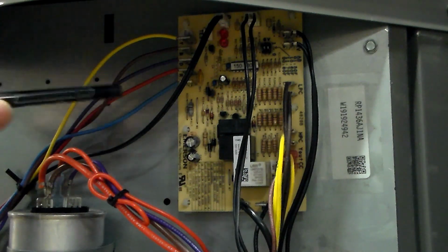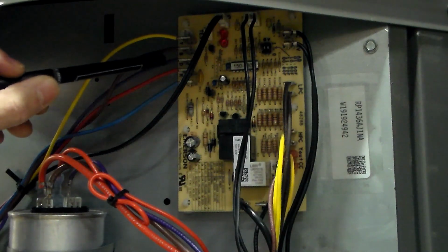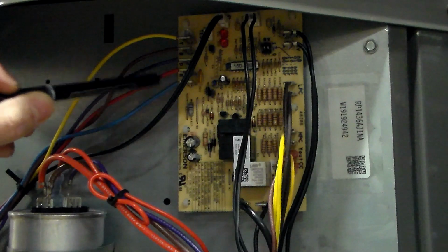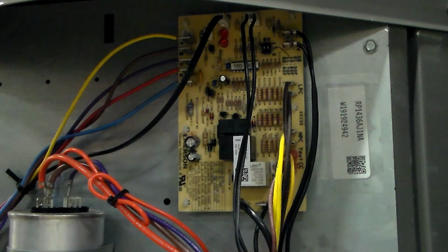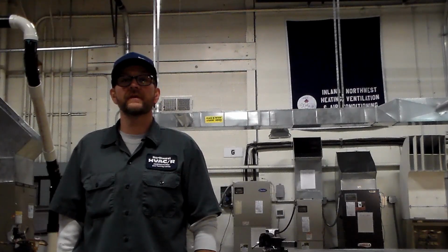You just have to understand that Rheem and Ruud do it backwards. They have the B instead of O, and they have D instead of W, but every other function on this board is exactly the same. You just have to remember that with Rheem, it's going to be sending 24 volts to the reversing valve during heating, and with everyone else, it's going to be doing that during cooling. And so, of course, from there we can deduce that during defrost, it's the opposite. So during defrost, Rheem is going to not send 24 to the reversing valve, and everyone else is going to be sending 24 volts to the reversing valve during defrost mode, because defrost is just cooling. So there you have it. Hopefully that was informative enough for you.